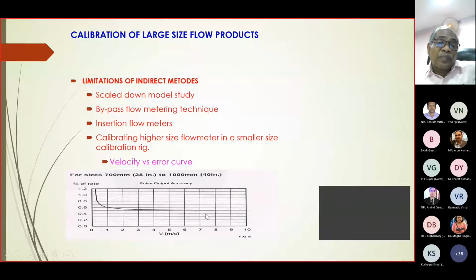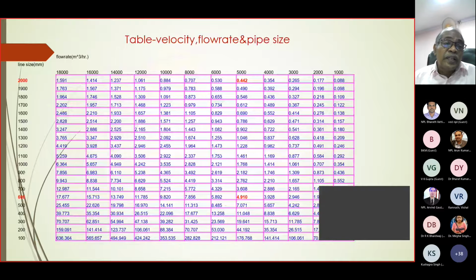Indirect methods. Okay, insertion flow meters are also not good. Then for calibrating, the existing pipeline is 600. If you have a 1000 mm meter for calibration, you have to fit it using an expander. But if you do that, you are not changing the flow rate because your flow rate is limited, but you are increasing the pipe diameter. So naturally the velocity will be less.